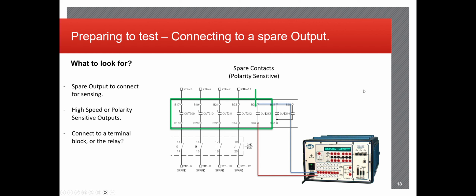So when we're doing our testing, most of the time when we want to pick up a specific relay logic element, something that doesn't trigger an output specifically from the relay, you'll end up hooking up one of your logic inputs to a spare output. In this case, it's polarity sensitive, so you want to make sure you're aware of that. But the reason we do this is when we're logged into the relay in the command prompt, you can set the spare output to equal whatever element you want to pick up. So what happens is when you run the test, that element that you're looking for picks up, it'll operate the output, and the test set will receive that output and mark it as a pass test.